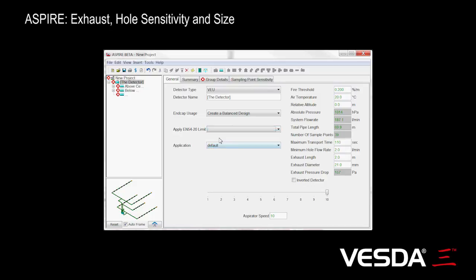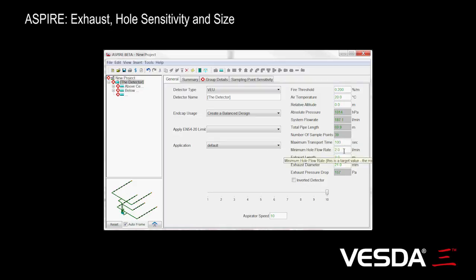It actually locks the transport time. Once you have a class B, class A, or class C setting, transport time is defined by that and you can't edit it. You can switch this off to essentially no EN54 20 limit, in which case your transport time can be edited up to the limit for that detector. So we could make this say 100 here.